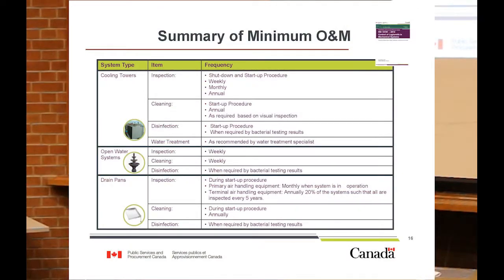So if we look at the summary of what the operation and maintenance activities are within our standard, I'll go through the cooling tower one in more detail, but maybe skip over the rest because there's a lot. For cooling towers, if we break it down, each system type basically has four main categories of maintenance actions: inspections, cleaning, disinfection, and then water treatment if there is a need for that. So for cooling towers, we have procedures for shutdown or startup of the towers, as well as weekly, monthly, and annual procedures for those towers that operate year-round and are not seasonally operated. We also require, at a minimum, cleaning at startup and annually for those systems, or as required based on those weekly or monthly visual inspections.